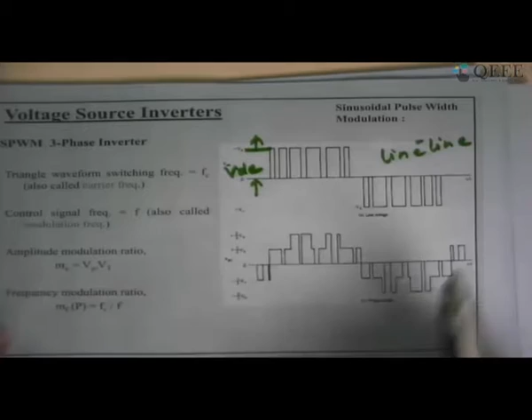Again, if we see the line to line voltage, it will not have a negative. You either get a plus VDC or you get a negative VDC. You don't get a bipolar signal; bipolar signal you'll get only in pole voltages. In line to line, when it's a positive cycle you will not get a negative, and for the negative half cycle you will not get a positive voltage. So this is a check you can do when you are actually operating an inverter. If it is like that, it is correct. If you are getting any negative pulses in the positive cycle, there is something wrong in the switching pattern.